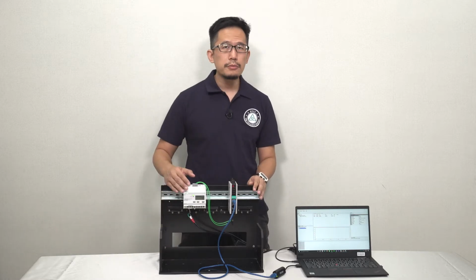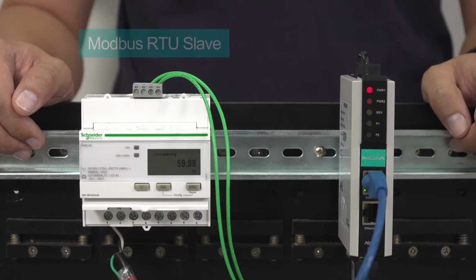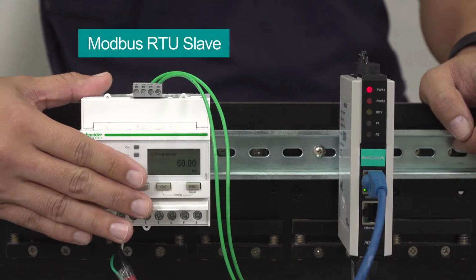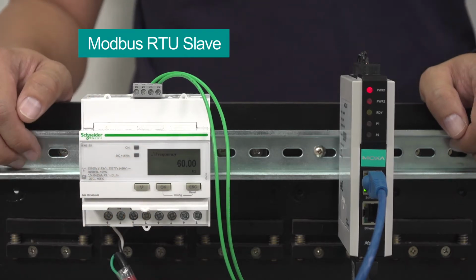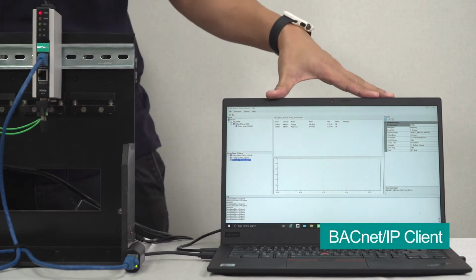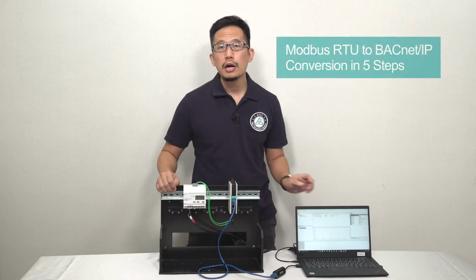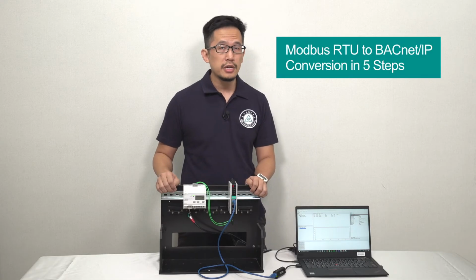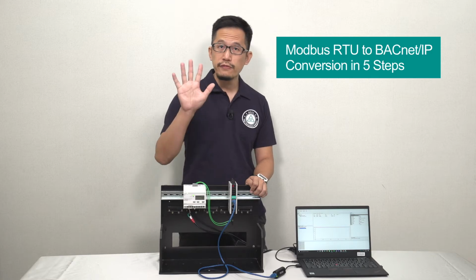To connect this power meter to our BACnet IP network, we have to convert Modbus RTU protocol, which the power meter uses, to BACnet IP protocol, which our BACnet IP client uses. I'm going to show you how to set this up with the Mgate 5217 in just 5 steps.